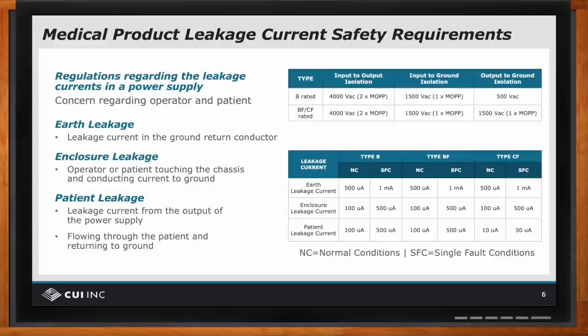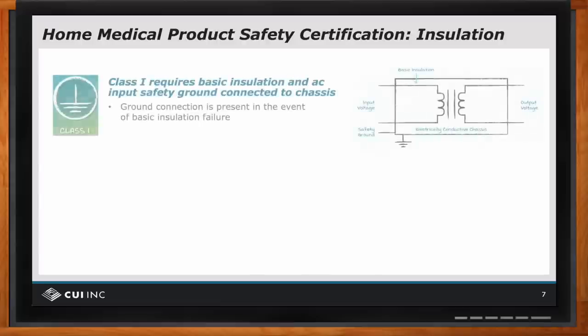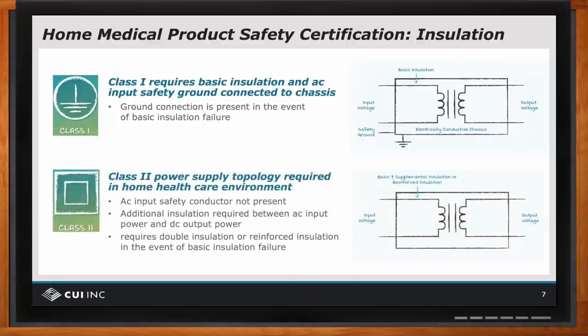Insulation is an important factor of safety, all to keep somebody from getting electrically shocked. There are two common classes of insulation. Class one has the AC input safety ground connected to the equipment, so only basic insulation is present inside — if that fails, the ground conductor carries the current away from the user. In class two, there is no safety earth ground, so you have two layers: basic insulation and a reinforced second layer. Importantly, home health care requires class two, because we can't be certain that an earth ground is always present in a home environment, whereas in certain commercial medical environments, class one equipment can be used.